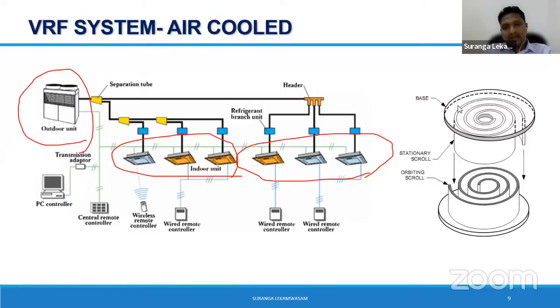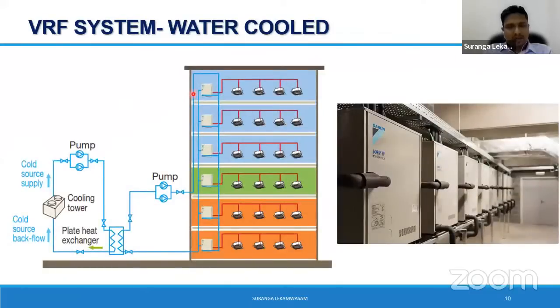VRF systems mainly use a compressor called a scroll compressor, right? The scroll compressors are varying the speed, and thereby you can vary the cooling demand in your VRF system. So this is basically air-cooled VRF that is common even in Sri Lanka. But over and above that, you can find water-cooled VRF systems as well. Yeah, not much common in Sri Lanka. I think only 5-6 installations at maximum are done here. But it is something good to look at for small scale applications if you cannot go for a chilled water system.